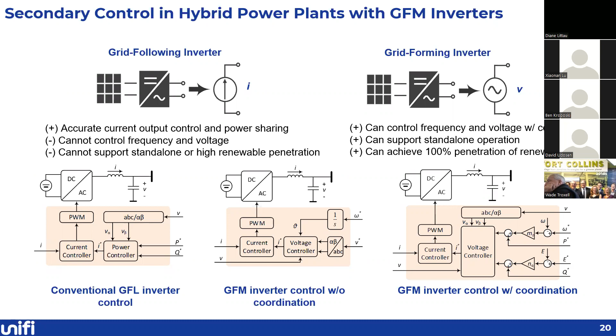What I'd like to say is, moving from conventional grid-following inverter control to grid-forming control with only frequency and voltage established, and further to grid-forming inverter control with droop control and coordination among local units, we can see how the technology evolves. For each type of control function, we may end up building different types of nodes using different control functions.